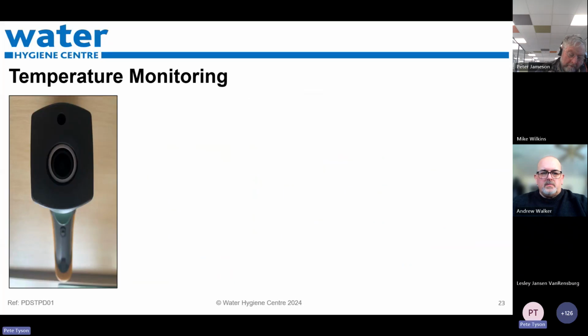We've also got these types of kit - this is an infrared probe, and unfortunately they've got their drawbacks. We need a tape with a specific emissivity value so the reflection of the laser can be removed from the result. And the position of the laser sight isn't where the temperature is actually taken.